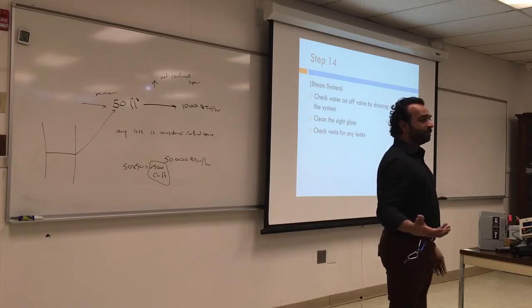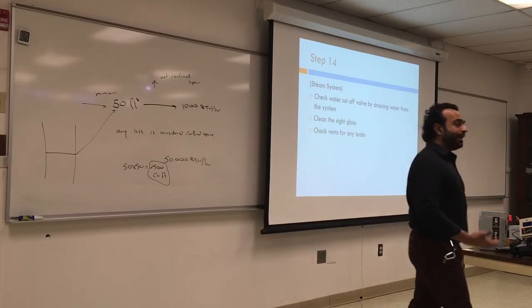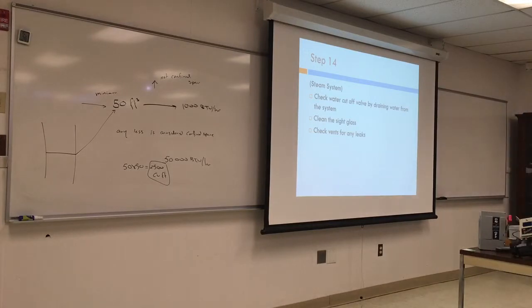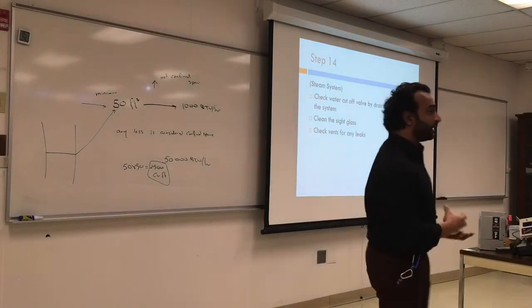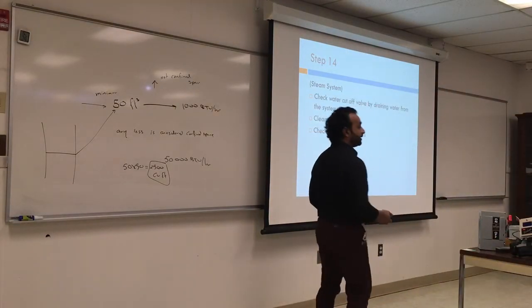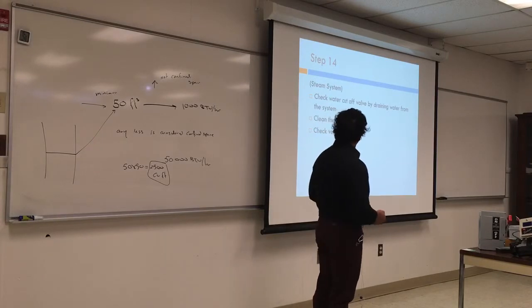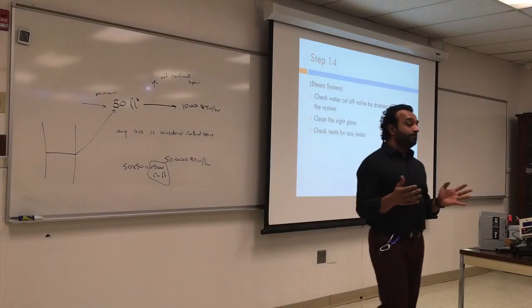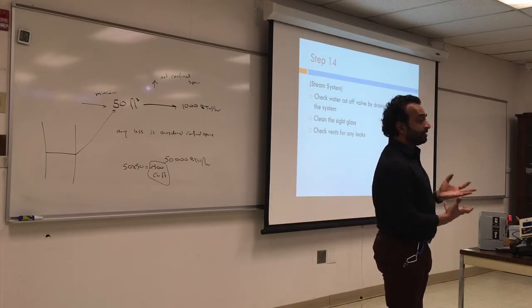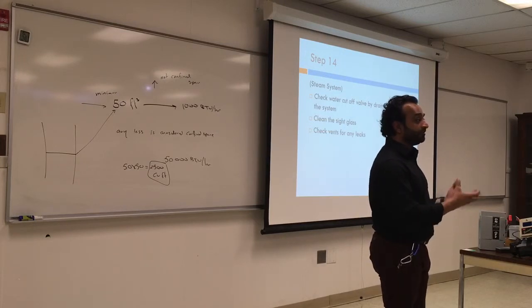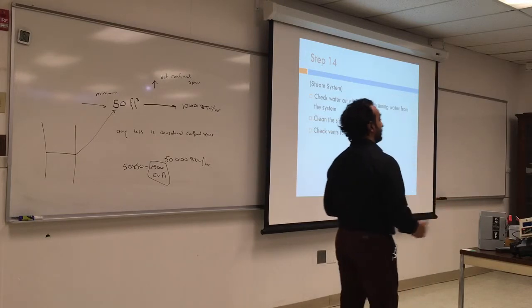So you drain the water, it comes really dirty. You want to change that periodically. What would happen if you don't? This will accumulate over time for hot water and for steam, and eventually it will clog the system. After a while, it will accumulate into a block, and the system will need to be cleaned and brushed. Also, the steam radiators, after a while, accumulate a lot of sediment in them that can clog because the opening is not big enough, and that could cause havoc. So you'll have to go there and clean them. So flushing the system periodically is very, very important.